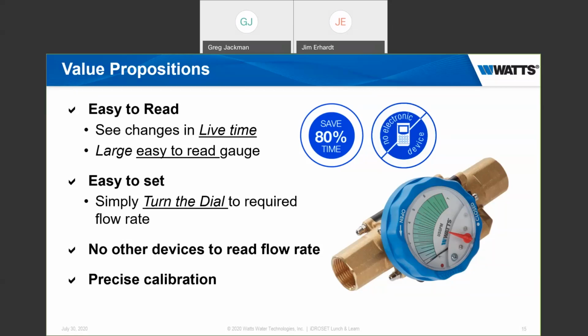On the photo, you'll see at about the 3 o'clock position on the blue handle, right by where it says closed, you'll see a small stainless steel set screw. Once you set the flow, you tighten that set screw and it locks the handle in place, so there can be no inadvertent changes to the flow rate. So no other devices are needed to read the flow rate, and precise calibration. We're going to talk about this. This is a really important aspect of the balancing process and also of the iDROSET valve.